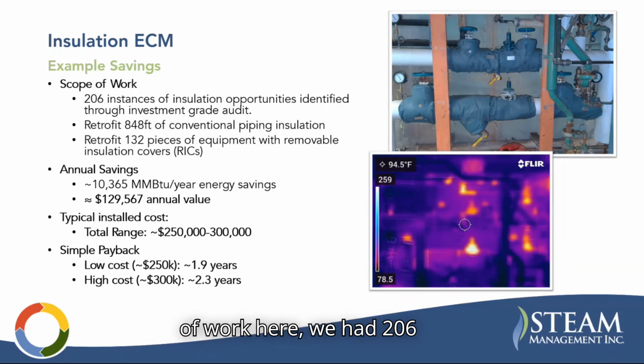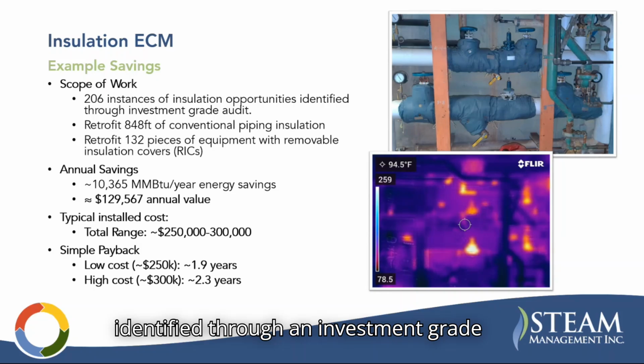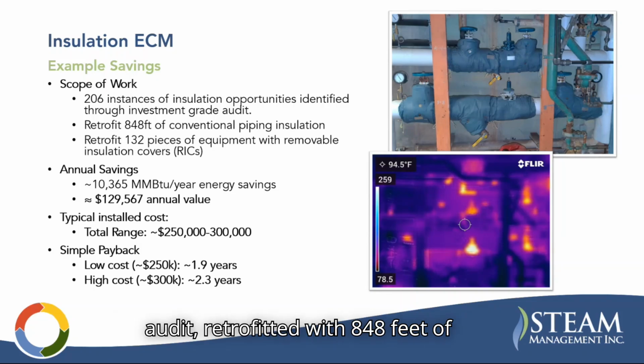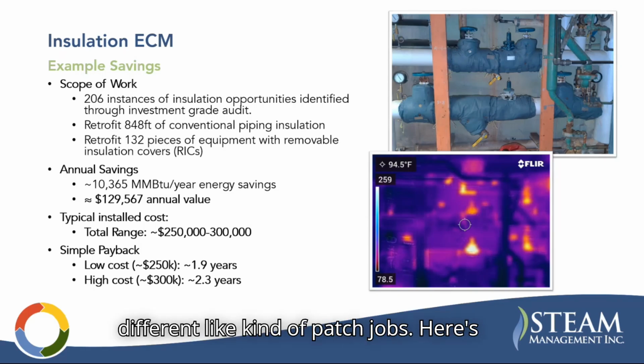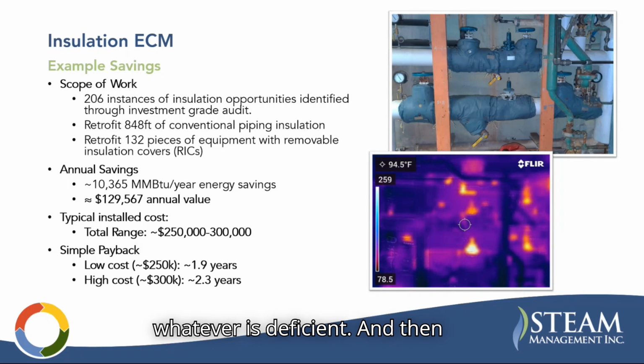The scope of work here: we had 206 instances of insulation opportunities identified through an investment grade audit, retrofitted with 848 feet of conventional piping insulation. Again, not all in the same place, just different patch jobs. Here's 5 feet, here's some fittings, whatever was degraded, come through and fix whatever is deficient. And then also retrofitting 132 pieces of equipment with removable insulation covers, which we call RICs, which is what we're talking about in the picture here.